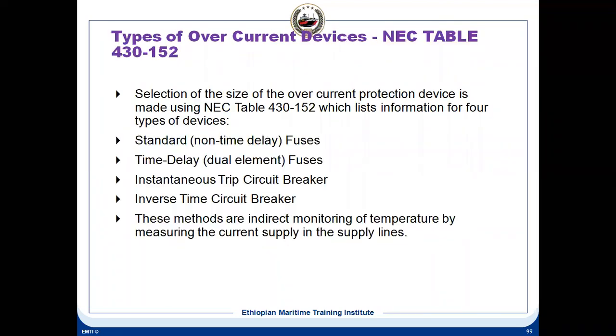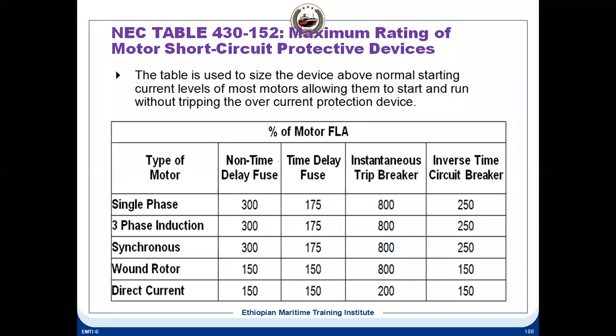Types of overcurrent devices. You see there are overcurrent devices: standard fuses, time delay fuses, instantaneous circuit breakers, inverse time circuit breakers. The selection of the size of an overcurrent protection device is made using the NEC table, which lists information for 4 types of devices. The table is used to size the device above the normal starting current level for most motors.